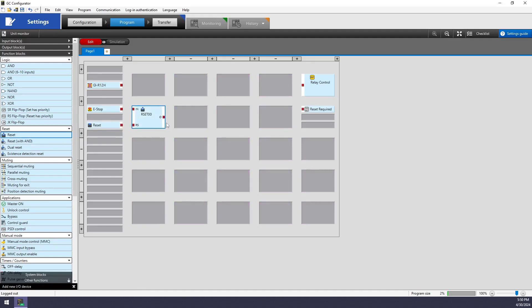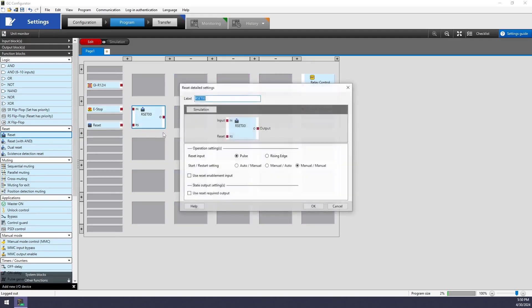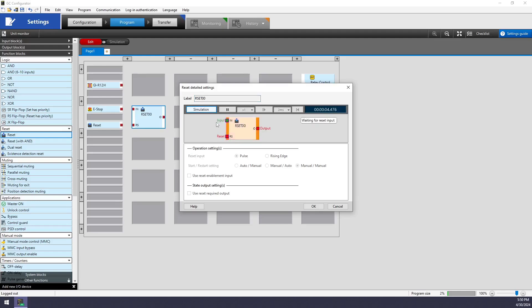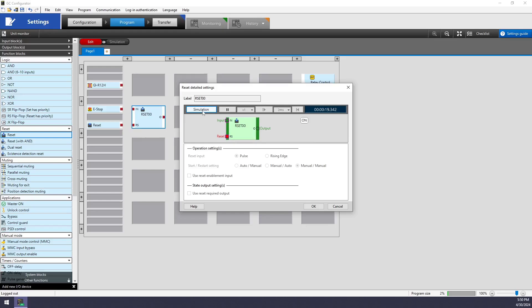Now, if I want to learn about this function block, I can right click on it and go into the detailed settings. There's two ways that I can learn about it. The first is sort of hands on. So I can click on the simulation button and you'll see these nodes become larger and I can actually click on them to toggle the input device and click on the reset to toggle the reset function. And now my output, it toggles on and off. So you can get a feel for how it's going to react whenever certain things turn on and off and how the output is affected hands on with the simulation.